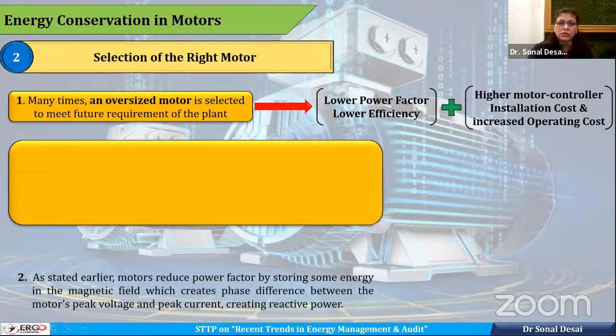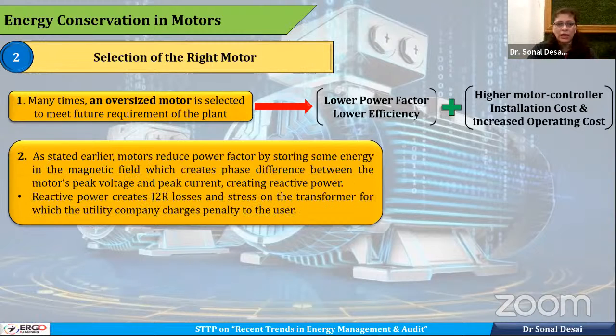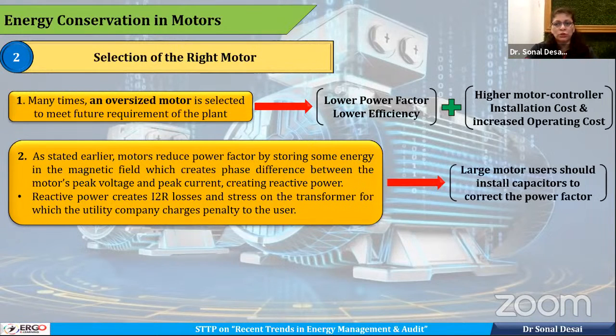As stated earlier, a motor reduces power factor, and that will create a magnetic field, which will create phase difference between peak voltage and peak current, and it will also create reactive power. So this reactive power ultimately creates I²R losses, stress on transformer, and for that, the utility company, maybe Maharashtra Electricity Board or any other board, will make a penalty to the end user. So large motor users should always install capacitors to correct the power factor.